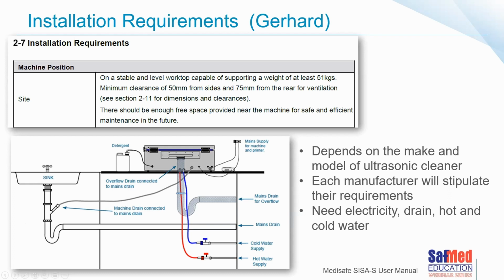Okay, this is an example of our machine, the MediSafe, which is more or less the same on most machines, but each manufacturer will stipulate their own installation requirement, which may differ depending on the make and the model of the device. The drawing is an example of the installation requirements for an automated ultrasonic cleaner. That means the machine is taking in hot and cold water, it's taking in its own detergent.